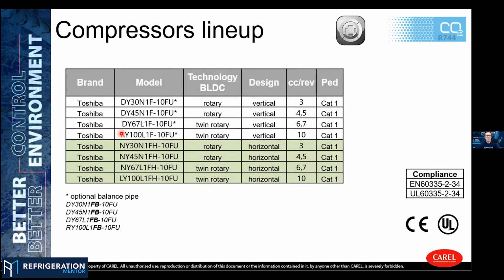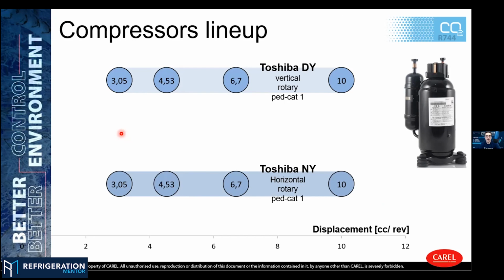Okay, you want to go back just for one second? There are a lot of people that haven't worked on twin rotaries. So what is that cylinder to the left side of the twin rotary compressor? Yeah, these are a suction accumulator and noise reduction. We can protect the compressor a little bit with a smaller suction accumulator, just to make sure that we are not flooding the compressor too much with liquid back from our application. It also has the function of reducing the noise of the refrigerant inside the compressor. So they have two different functions.